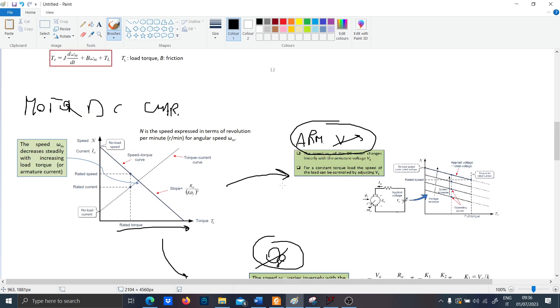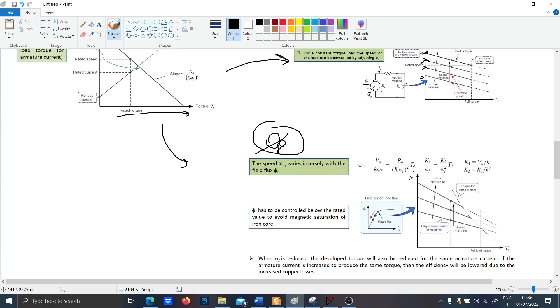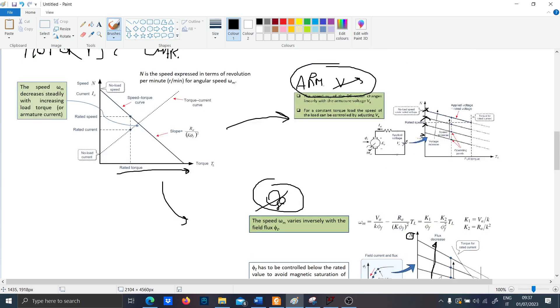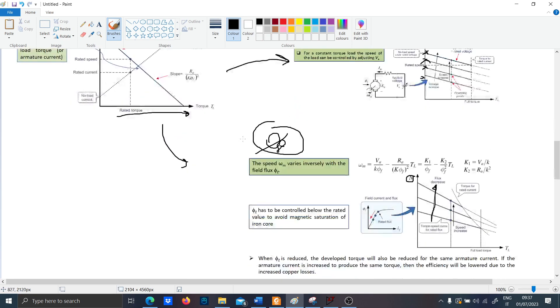With armature voltage control, the higher the voltage applied, the higher the speed — but naturally this decreases with load. If you vary the flux instead, as you decrease the field flux inside the DC motor the speed will increase. These are the two methods of controlling speed, and naturally you have to compensate with a PI or PD controller — though PD is seldom used.